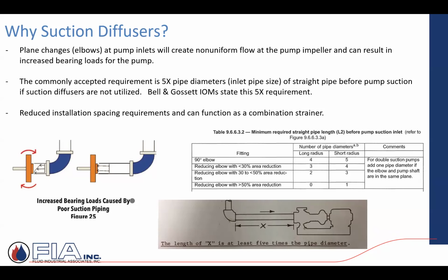And from that elbow, when I make that change, there's different velocity taking place. The flow rate, as soon as you make that plane change, isn't equal, if you will. What they refer to maybe as a non-uniform flow pattern. And if that was to hit the impeller, that would load the impeller unevenly. And if you think about the impeller, what's behind it is the seal, a shaft, a bearing assembly, and you're really wreaking havoc with the life expectancy, the function of that pump shaft steel. And the industry's known that for years. And the way they addressed it is they said, hey, I want a straight run of end suction pipe diameter, a straight run of pipe to straighten out that plane change.